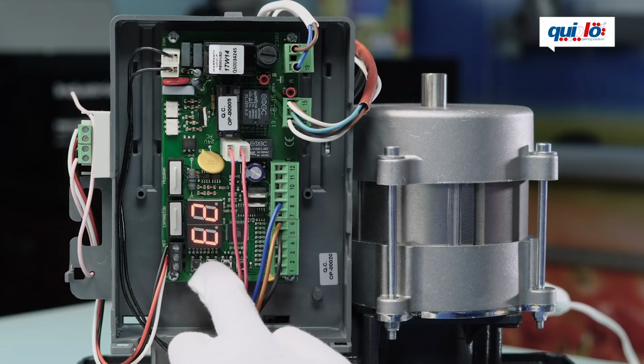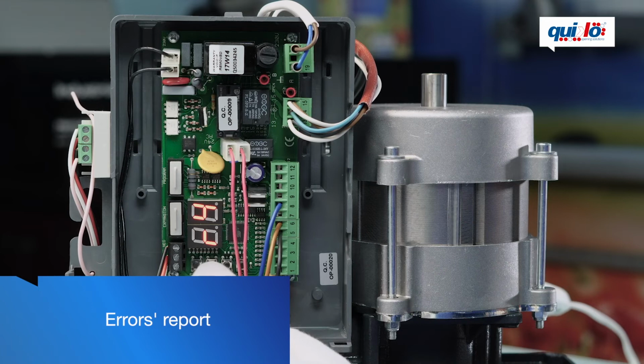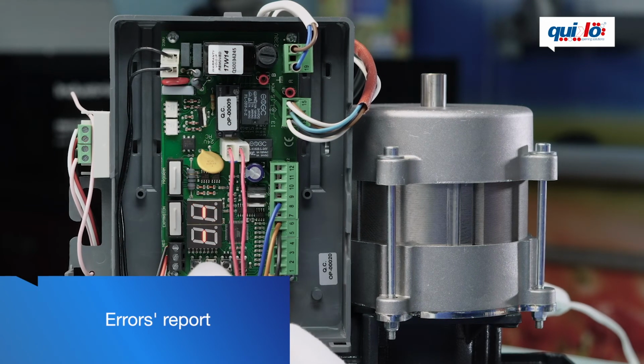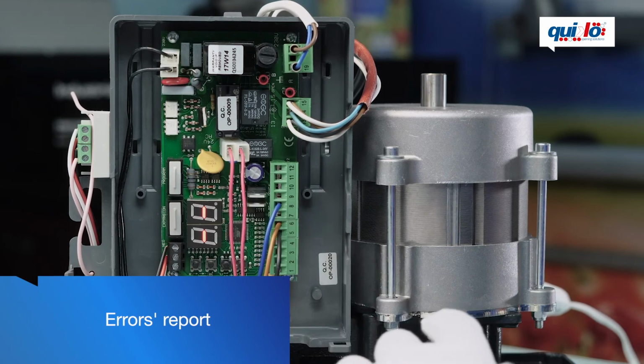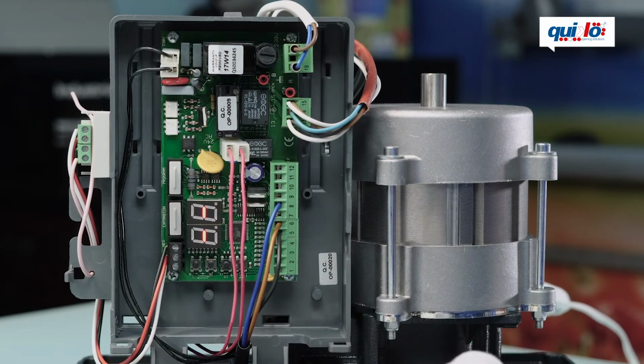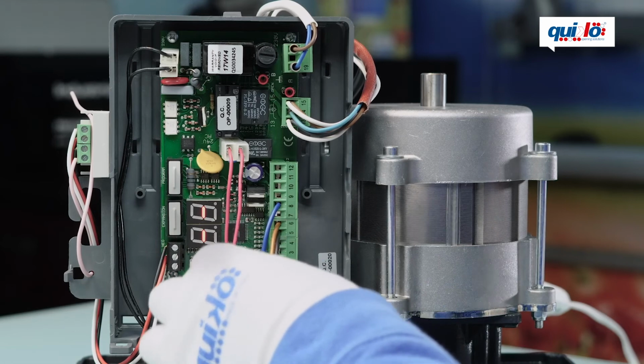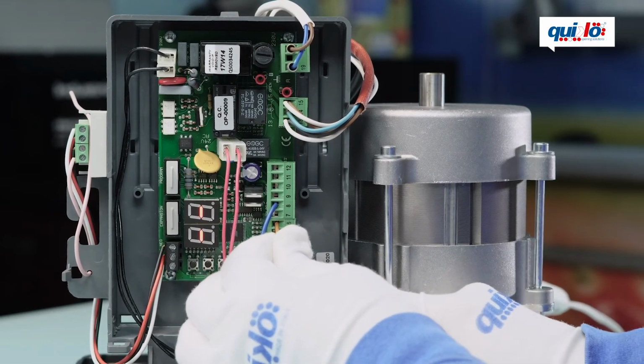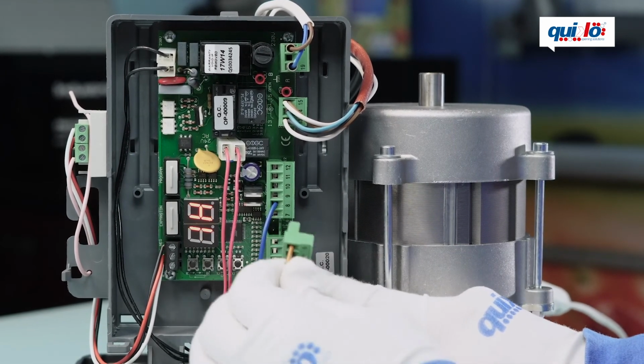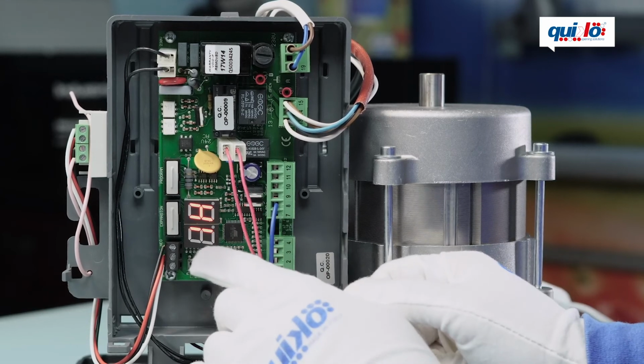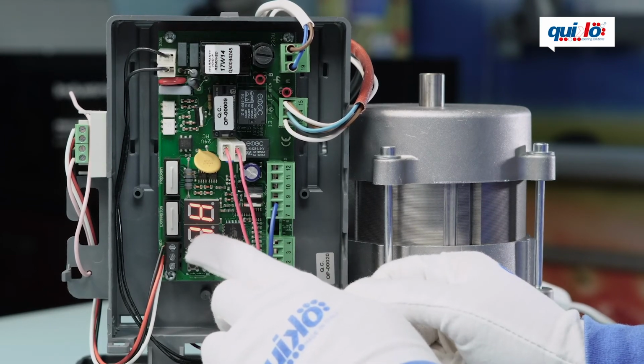We will now see the error report, because as per the user manual, the control board during standby shows if there are some errors. For example, I will now remove the limit switches connection. You will see the board will detect an error, IH.